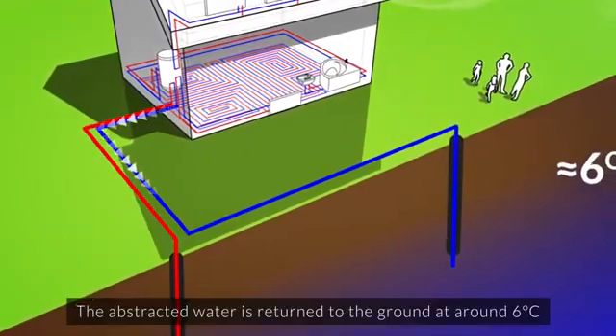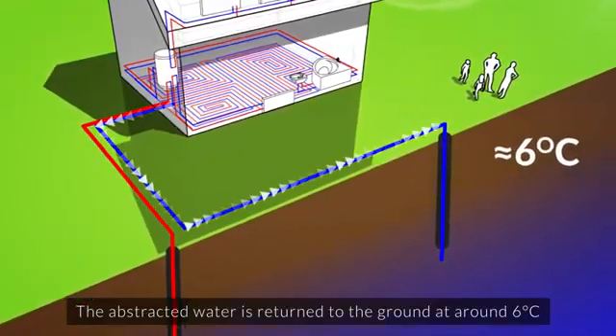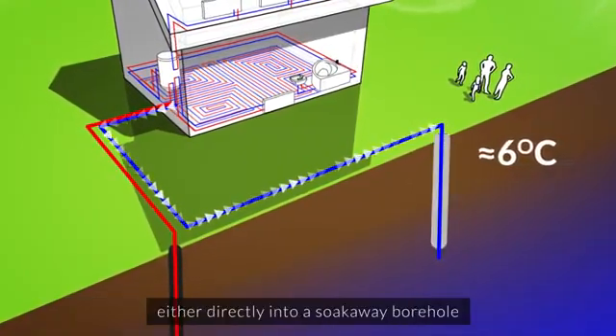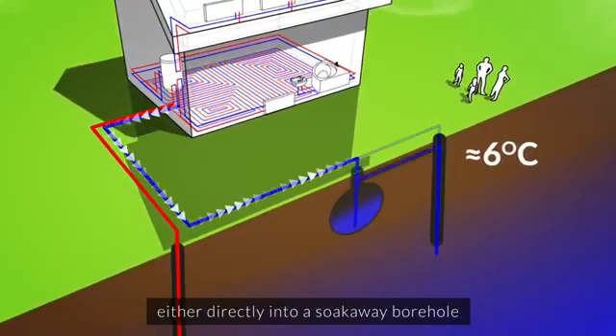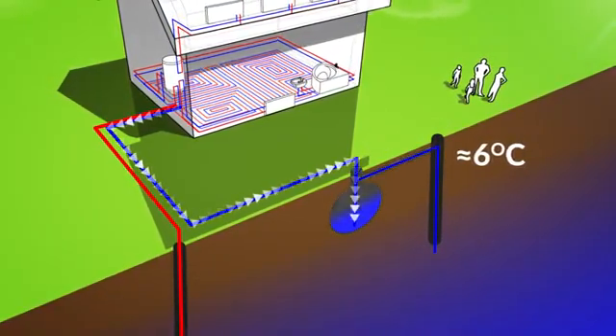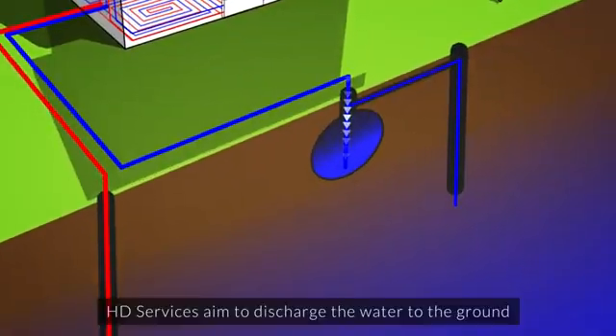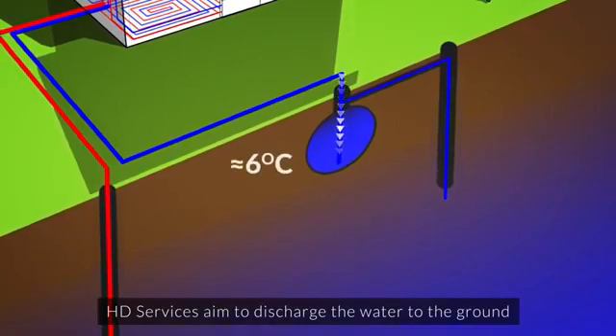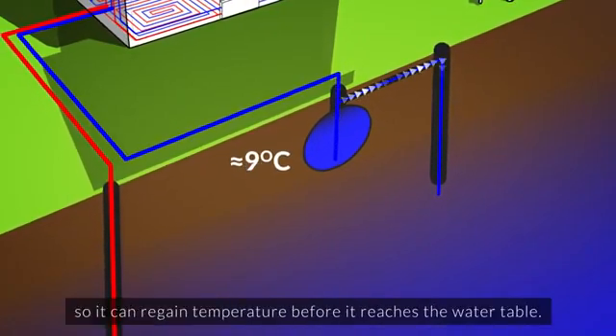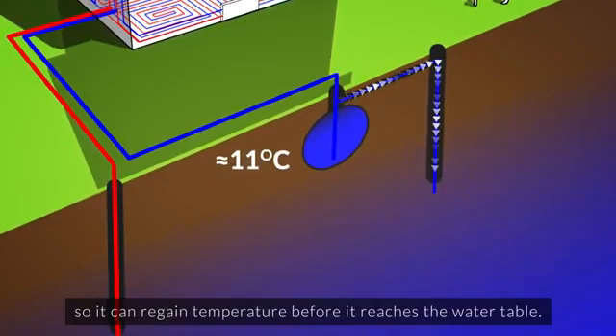The abstracted water is returned to the ground at around 6 degrees Celsius, either directly into a soak away borehole or via a water harvesting tank. HD services aim to discharge the water to the ground above the water table so it can regain temperature before it reaches the water table.